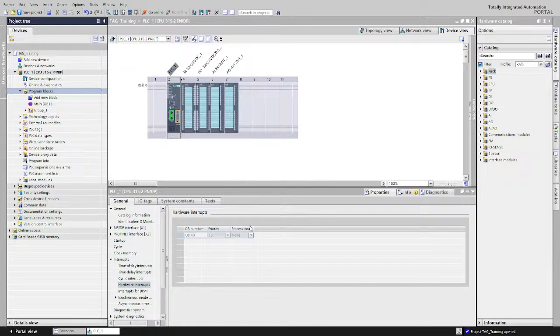A very poor way of programming a system is, for instance, you have a bus cable or an Ethernet cable connected to a drive or another system, and if you unplug that cable, the whole machine stops. That is not a safe way of programming a system. It should not stop all your system. It should just give you an alarm unless it is a critical input, in which case it can stop the system.